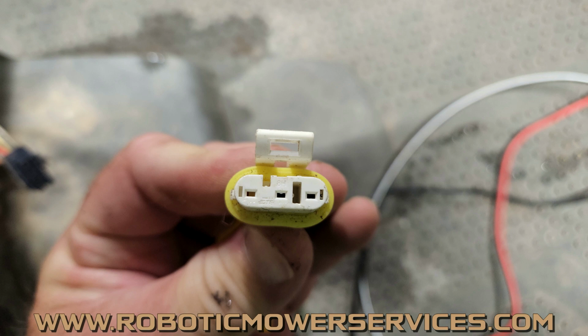Now, I will warn you, if you go to try to test the male end of your low voltage cable, you are going to need some smaller probes to stick in there or some kind of adapter to stick in there, because the probes from almost every multimeter out there just do not fit in these holes. So make sure you have something on hand so you're getting in there and getting good contact with the connectors inside this plug when you test for your resistance.